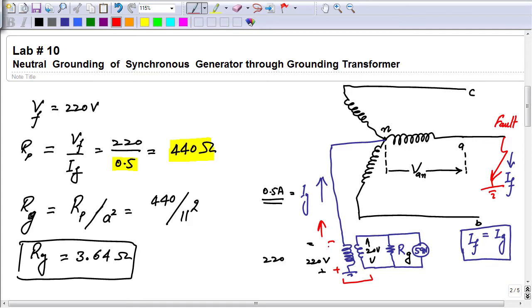So that will result in a very little voltage appearing across this RG resistance during normal operating condition. We can set the pickup value at 2 times of that value to make sure that the relay is not tripping during the normal condition.